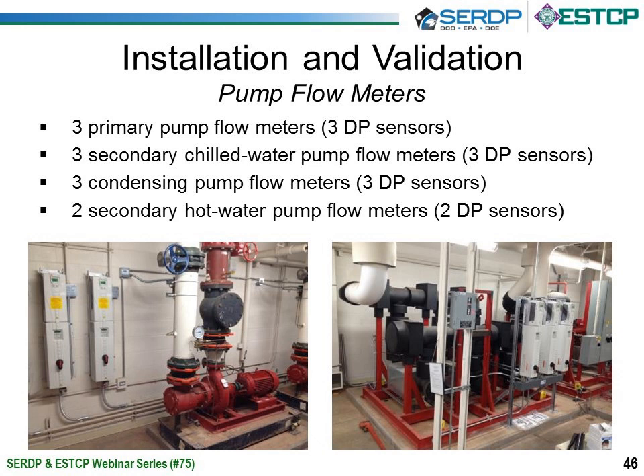We've installed pump flow meters for the pumps indicated here, 3 primary chilled water flow meters, 3 secondary chilled water pump flow meters, 3 condenser pump flow meters, and 2 secondary hot water pump flow meters. This allows us to monitor these flows through virtual sensing.